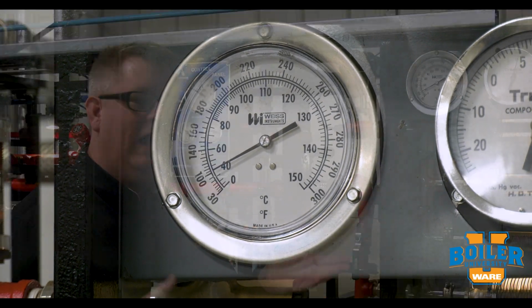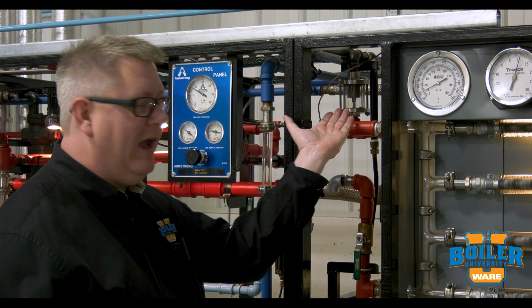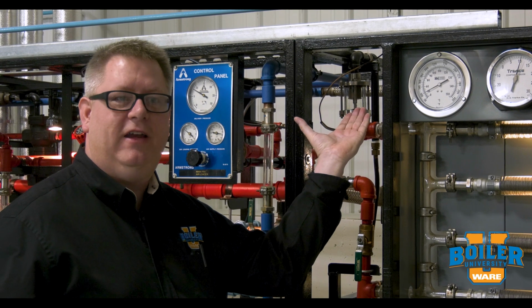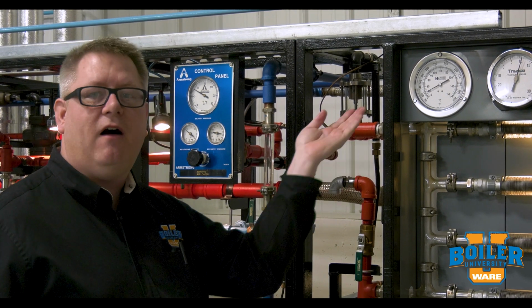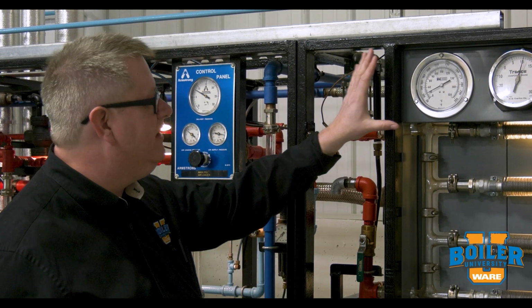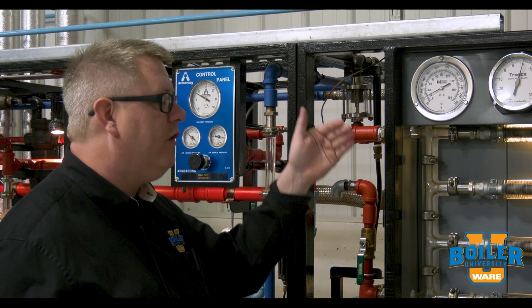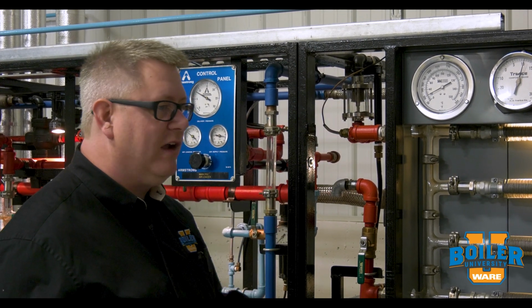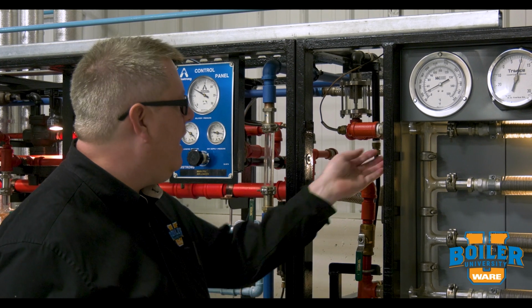One thing we can do to assist additionally is put an air vent on the high point of heat exchangers. So I'm going to open the valve to this air vent and we'll quickly see that temperature climb. We'll also see a much larger amount of condensate coming through our trap.